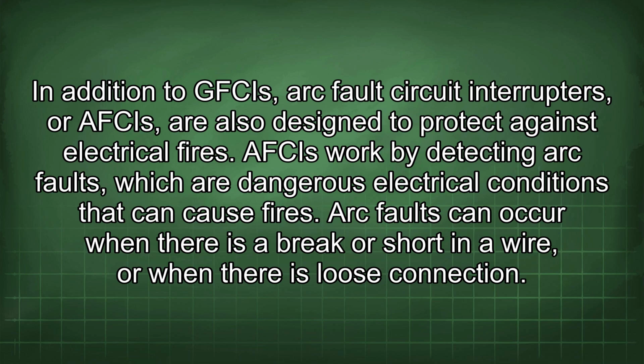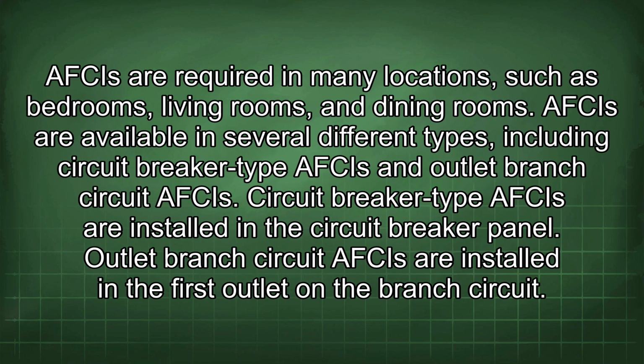In addition to GFCIs, arc fault circuit interrupters, or AFCIs, are also designed to protect against electrical fires. AFCIs work by detecting arc faults, which are dangerous electrical conditions that can cause fires. Arc faults can occur when there is a break or short in a wire, or when there is a loose connection. AFCIs are required in many locations, such as bedrooms, living rooms, and dining rooms. AFCIs are available in several different types, including circuit breaker type AFCIs and outlet branch circuit AFCIs.